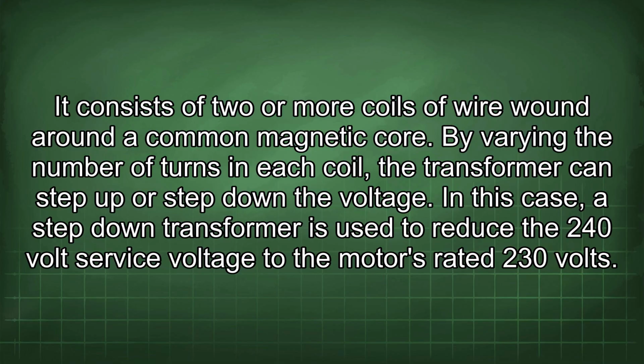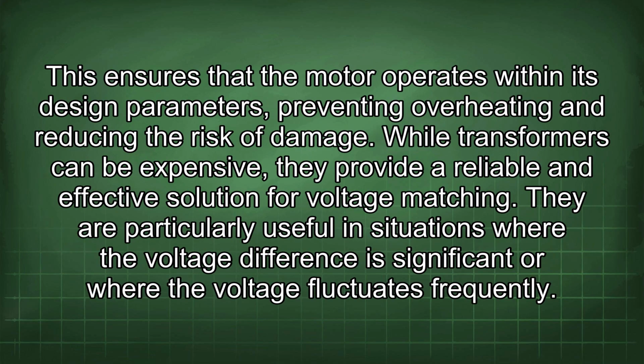In this case, a step-down transformer is used to reduce the 240-volt service voltage to the motor's rated 230 volts. This ensures that the motor operates within its design parameters, preventing overheating and reducing the risk of damage. While transformers can be expensive, they provide a reliable and effective solution for voltage matching. They are particularly useful in situations where the voltage difference is significant or where the voltage fluctuates frequently.